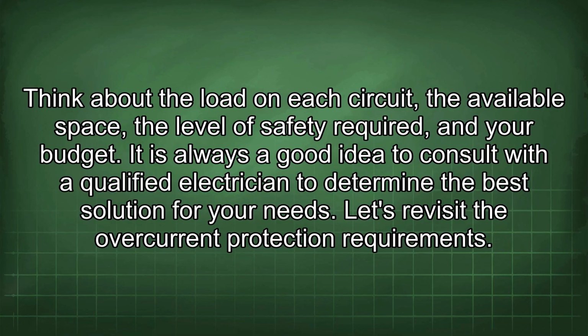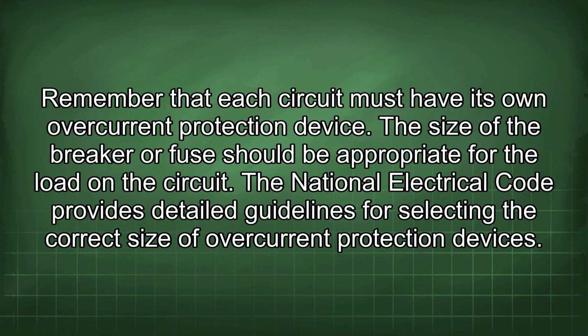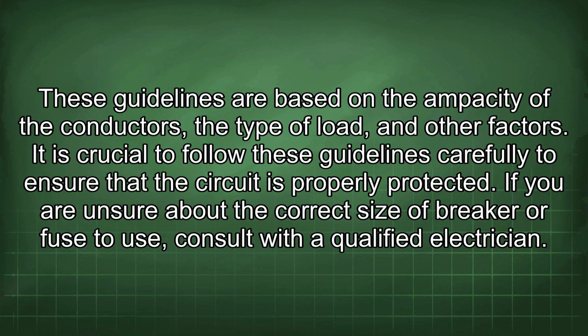Let's revisit the overcurrent protection requirements. Remember that each circuit must have its own overcurrent protection device. The size of the breaker or fuse should be appropriate for the load on the circuit. The National Electrical Code provides detailed guidelines for selecting the correct size of overcurrent protection devices. These guidelines are based on the ampacity of the conductors, the type of load, and other factors. It is crucial to follow these guidelines carefully to ensure that the circuit is properly protected. If you are unsure about the correct size of breaker or fuse to use, consult with a qualified electrician.